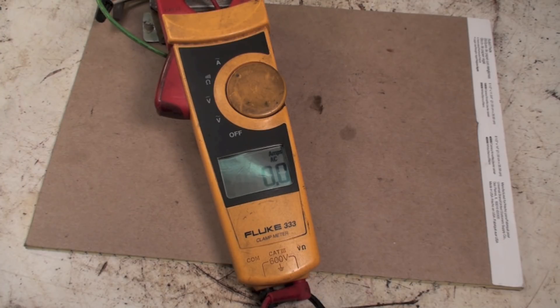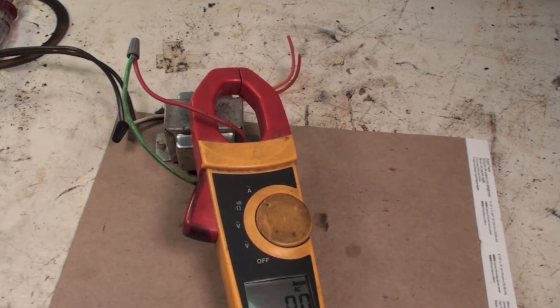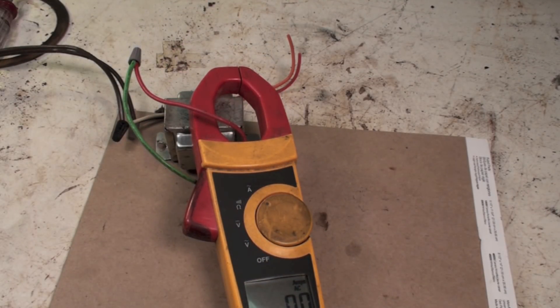Okay, eight amps is way too much. If it's a 40 VA transformer, it'll do about 1.6 amps. You can use the E-I-R formula for this if you want, but 40 VA is a very common transformer, and so it should be about 1.6. Well, it's eight. If it's eight, it's not going to work - it's going to burn it up just like the other one did.